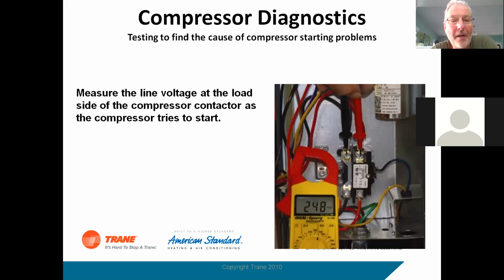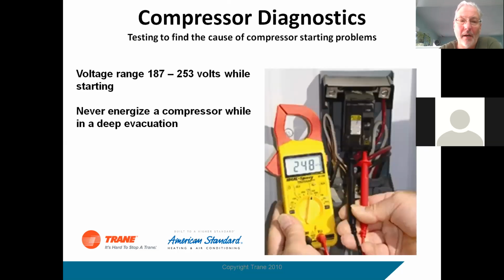With the voltage on, measure the voltage at the load side of the compressor as the compressor tries to start. The next slide will show this, but if it drops below a certain voltage, this compressor may not start. So, at rest, you may have 220 volts, but if you try to start that compressor and it drops below 187, that compressor may not start. You have a voltage issue at that point.